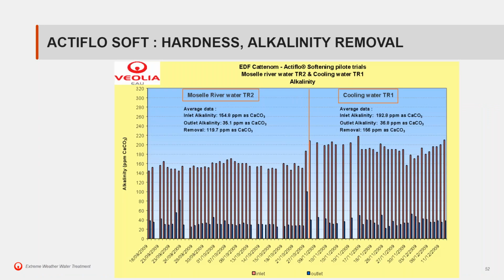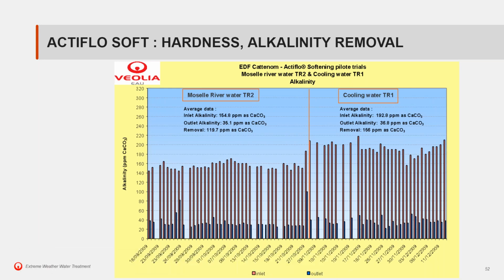Some data on Actiflo Soft. Why? Because it's purely chemistry. You have the record here in terms of alkalinity of the raw water and alkalinity of the treated water. We are able with Actiflo Soft to go down, by dosage of lime or caustic, to the solubility of CaCO3, down to 20, 30 milligrams per liter as CaCO3 on demand, and that's directly matched with the dose of lime.